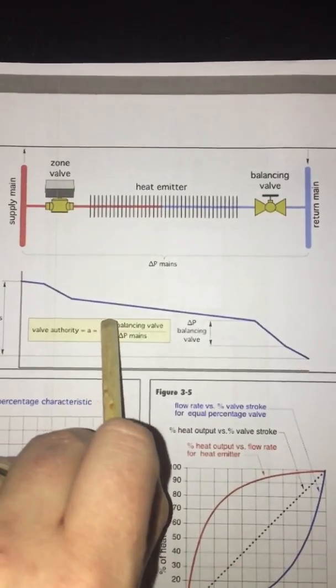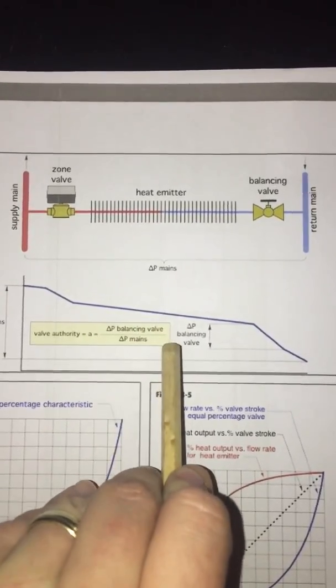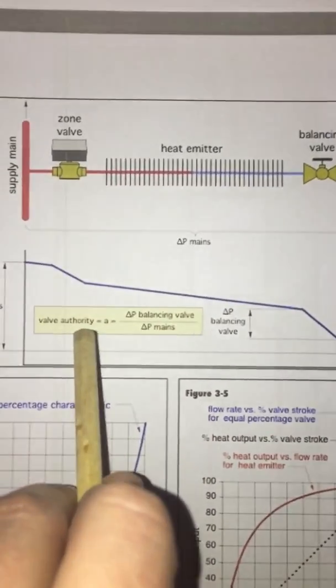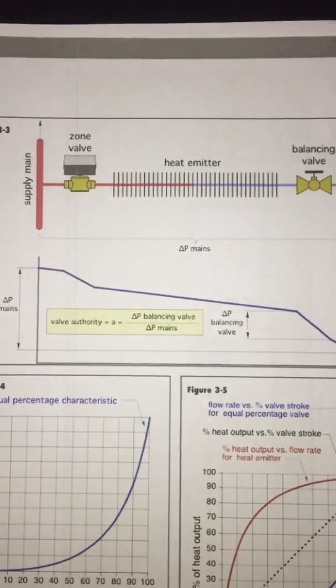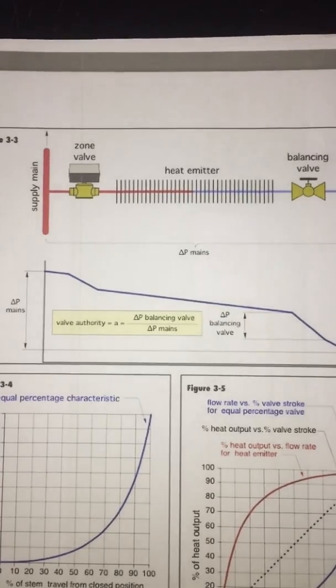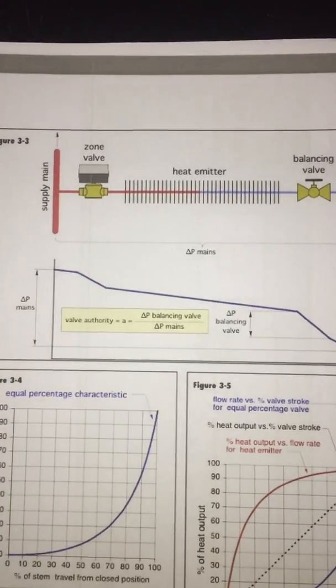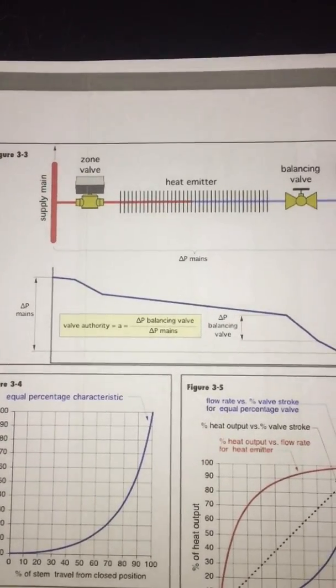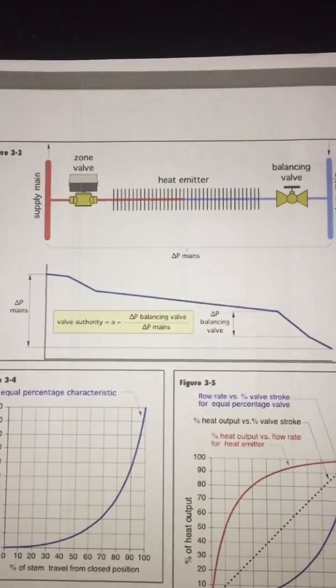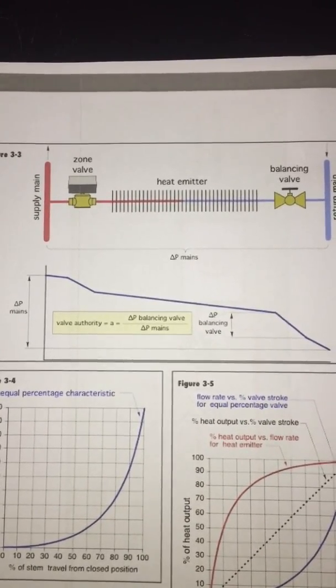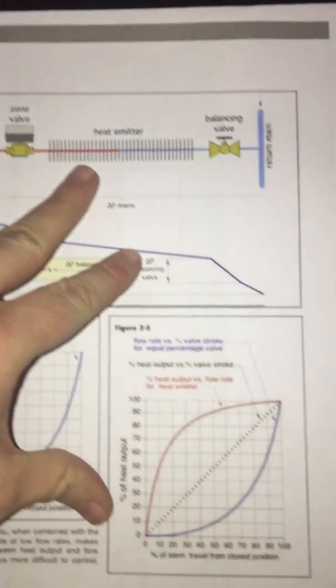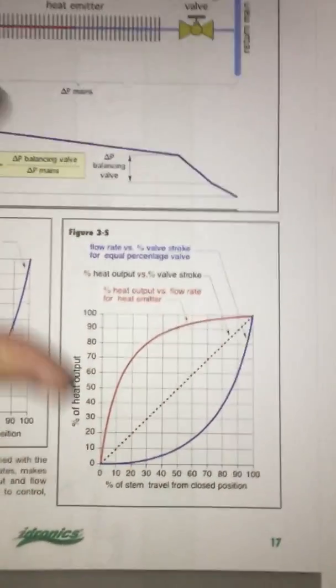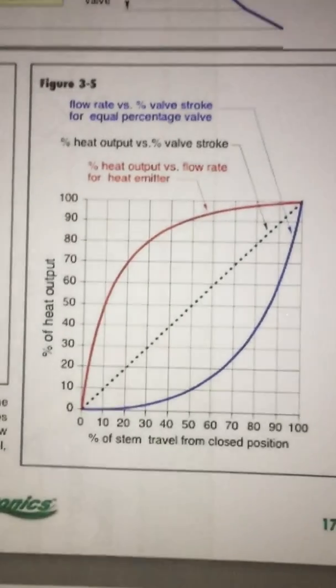So if we get the delta P of the balancing valve divided by a delta P of the mains, we'll have that valve authority figure that we want to be between 0.2 and 0.5, or between 20 and 50%. If it's more than 50% of the resistance of the total circuit, that could be considered uneconomical in terms of pump energy, or below 20% would definitely give poorer flow control, which is represented by this graph here.